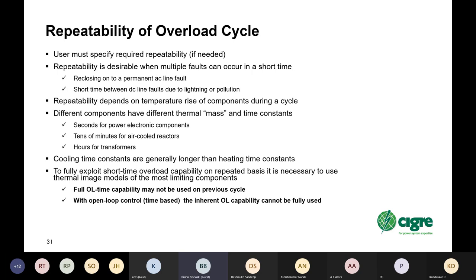Repeatability depends on the temperature rise of the components during any overload cycle. Different components have different thermal mass and thermal time constants, which are in the order of seconds for power electronic components, tens of minutes for air-cooled reactors, hours for transformers. Cooling time constants are generally longer than heating time constants. This is something which is sometimes not appreciated, and in particular, larger components have much longer cooling time constants than heating time constants. You can always heat something up quickly by putting a lot of current into it, but cooling has to occur due to, in some cases, convection to air or convection to soil for electrodes and things like that. And those time constants can be fairly long.